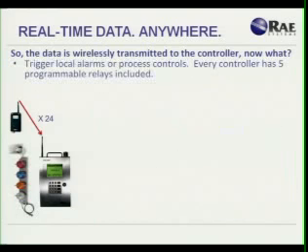So the first thing we talked about is that you have 5 internal relays. You can use those to drive lights and horns. We also know that a lot of you folks are using it to drive process controls, to turn on fans, to shut down processes, to do other things that are related to the safety measures. The controller by itself has that built in as a standard feature. You have those relays that you can use to trigger different processes or alarm conditions.